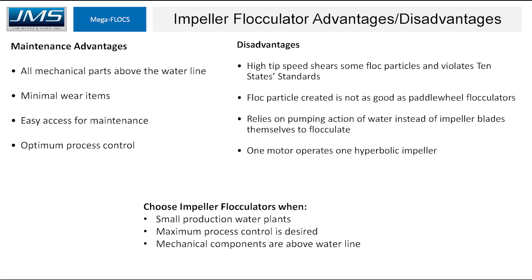Some advantages of impeller flocculators are that all mechanical parts are above the water, minimal wear items, easy access for maintenance, and you can control the speed of each unit. Disadvantages are that high shear zones violate the Ten State Standards, the floc is not as high quality, and it relies on the pumping action of the blades rather than the blades themselves. One motor operates one unit, which doesn't spread gearbox cost. These are ideal for small production water plants where maximum speed control is needed and all mechanical components must be above the water line.